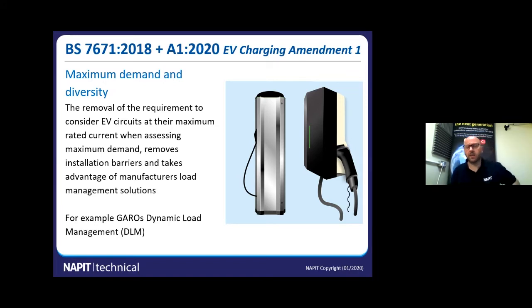Okay, that's fantastic, Conor. Really, and that's all automatic. The customer doesn't have to change anything, get involved at all. It just happens automatically. Yes. Yeah, providing the install is set up correctly on the day of setup, yes, that will be an automatic solution. As car 1 connects, it's 32 amps. Let's say we've got it set for a 3-phase 100 amp scenario.